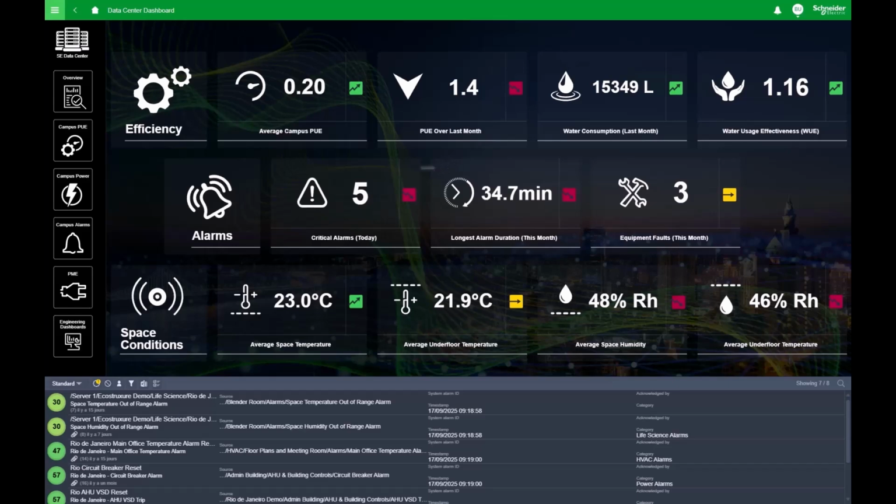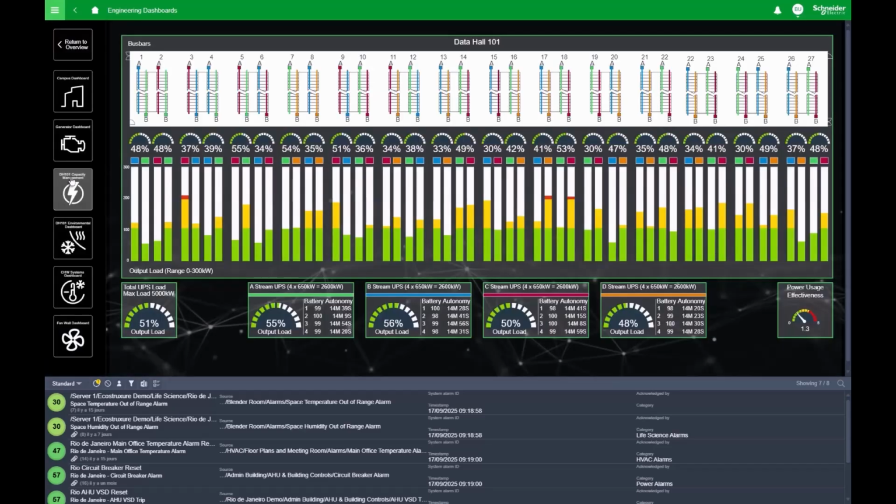We also have capacity management dashboards, which of course are meant to easily visualize the capacity metrics within our data hall. We can see that we can monitor directly on the busbar level, but also we can use the EcoStruxure tools to look upstream to our UPSs to ensure that we have resilience as we expect in the data center. In tandem, we can also have alarms generated when we're approaching any capacity limits that we've defined, as well as visualize them here on the dashboard, as we can see in these examples. So the intent behind this dashboard, of course, is to provide an easy and intuitive visualization to see how close we are to failover.